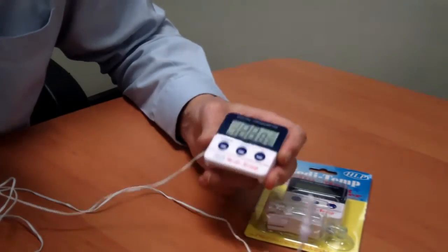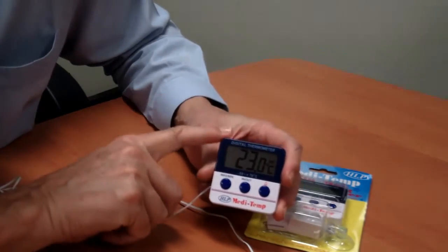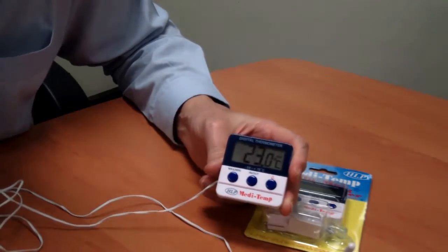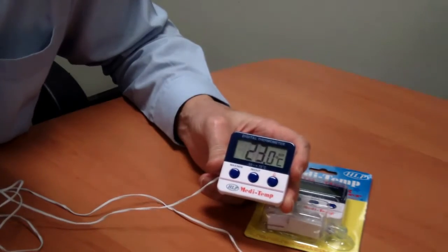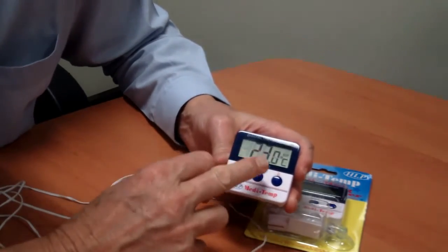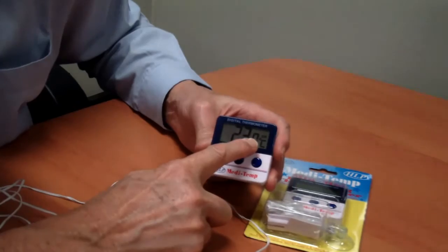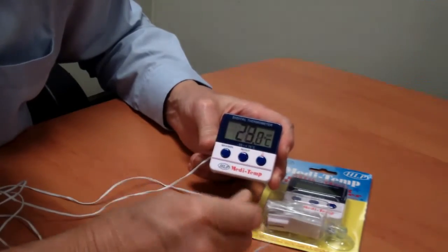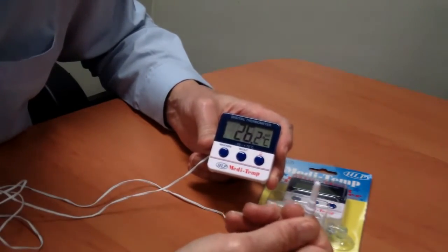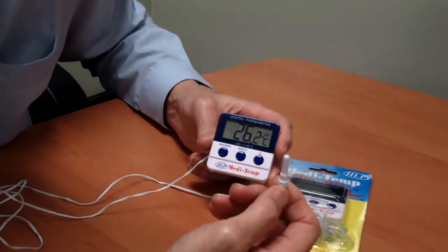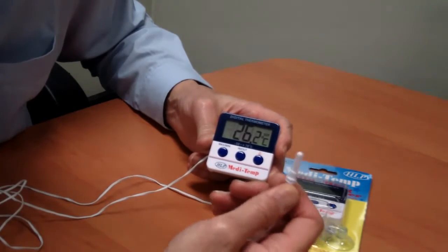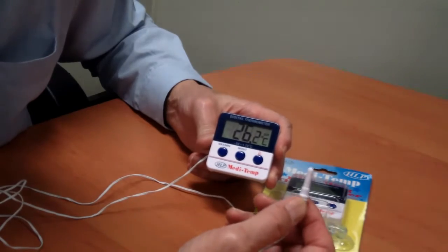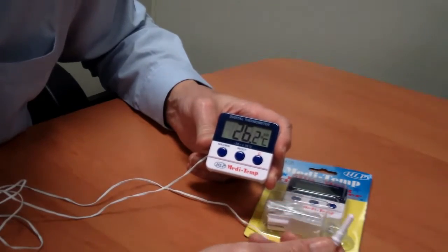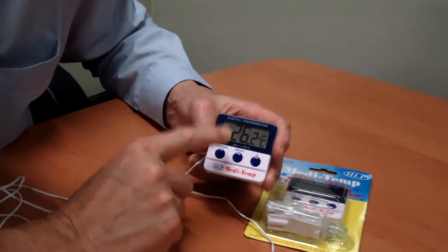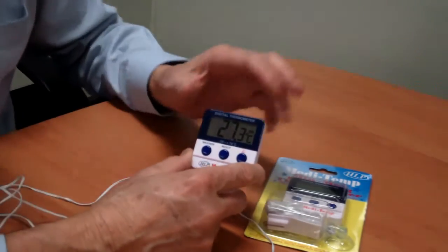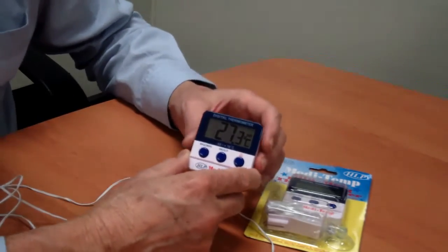Now, this has got 2 temperature sensors in it. One is in the unit and one is out on the wire. So when you're looking at the temperature display, it's got out and it's got a temperature. So out is actually the temperature display on the outside wired temperature probe. So that would be the one that's in the fridge. If this display says in, then it's actually just reading the temperature of the unit. So you need to change it.